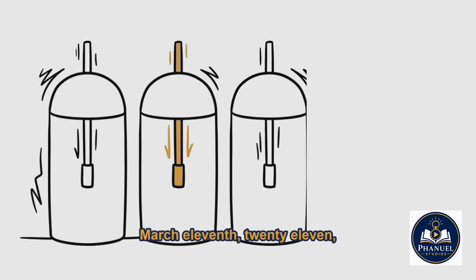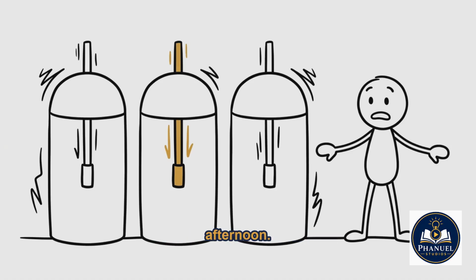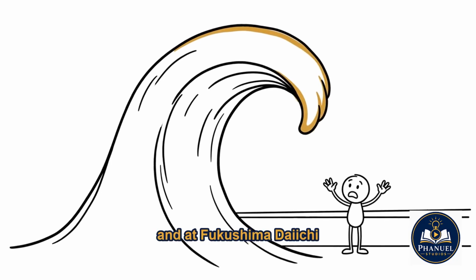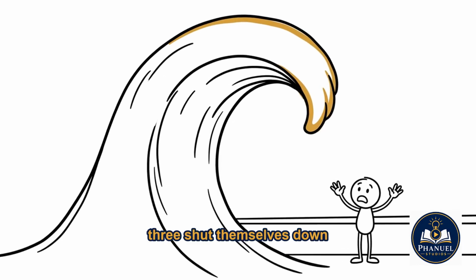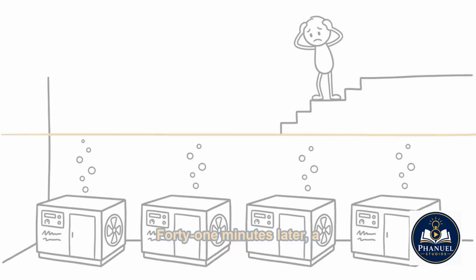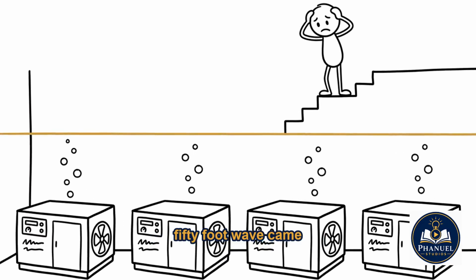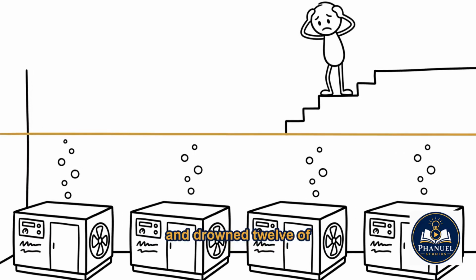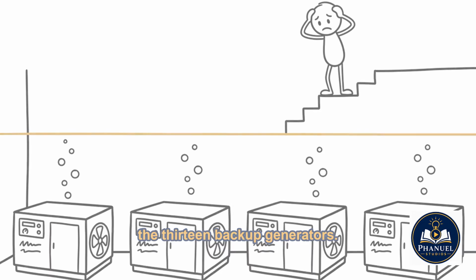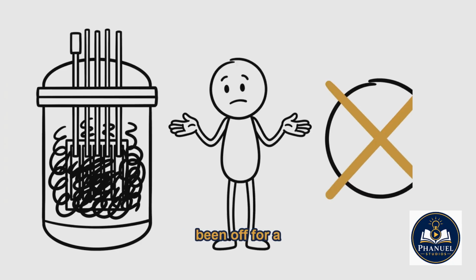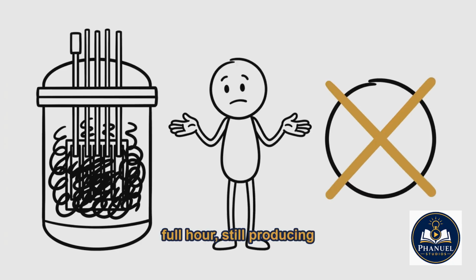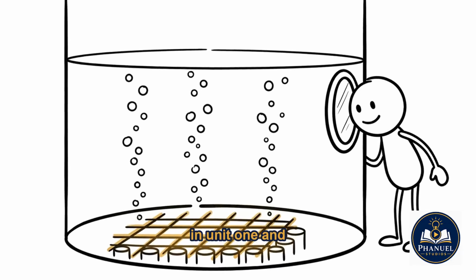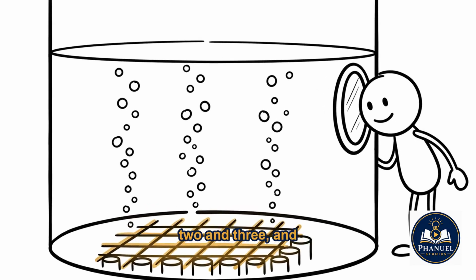March 11th, 2011, 2:46 in the afternoon. The largest earthquake in Japan's recorded history hits, and at Fukushima Daiichi, Units 1, 2, and 3 shut themselves down automatically, exactly as designed. That part worked. 41 minutes later, a 50-foot wave came over the seawall and drowned 12 of the 13 backup generators. So now you have a core that has been off for a full hour, still producing 22 megawatts of heat in Unit 1 and 33 megawatts in Units 2 and 3, and nothing left to push water through it.